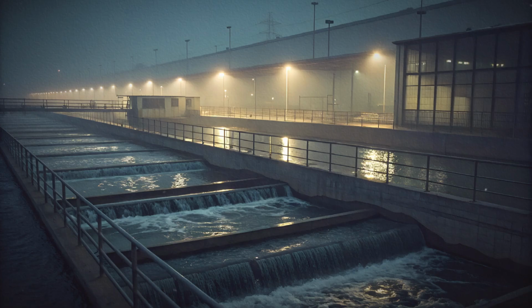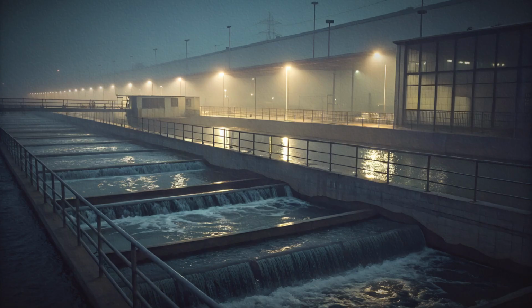Control systems monitor intake conditions continuously. Sensors measure water level, flow rate, turbidity, and sometimes basic chemical indicators. Alarm thresholds alert operators to conditions that require attention, such as sudden increases in turbidity or reductions in flow. Automated controls can adjust gate positions or pump speeds in response to sensor inputs. Manual interventions remain part of regular operation, especially during maintenance or unusual events.